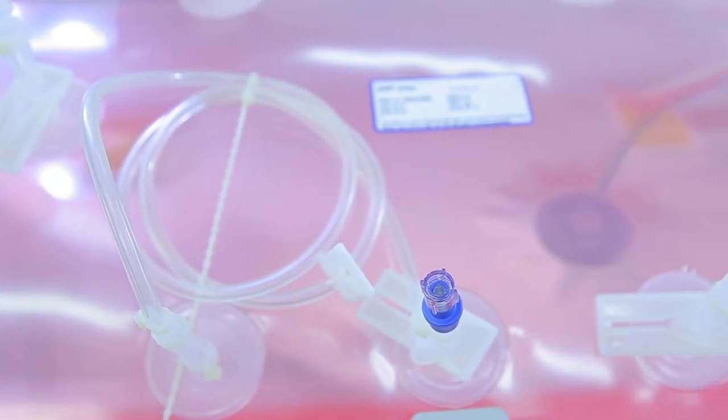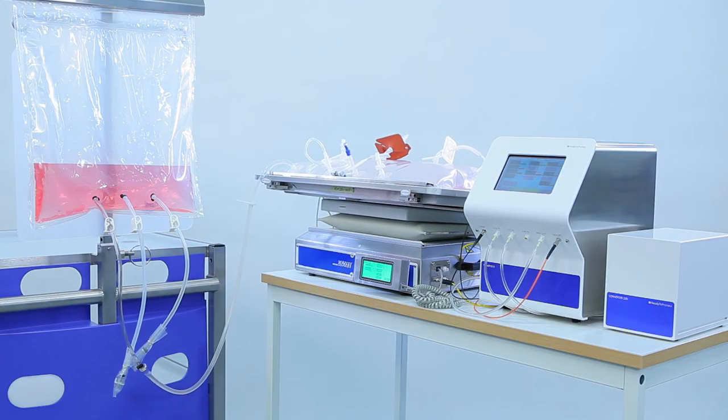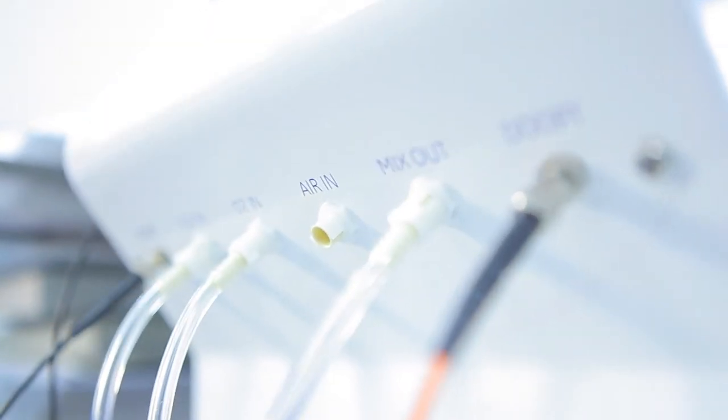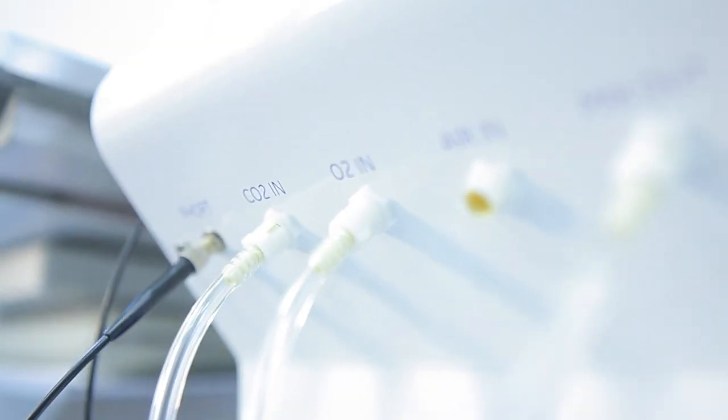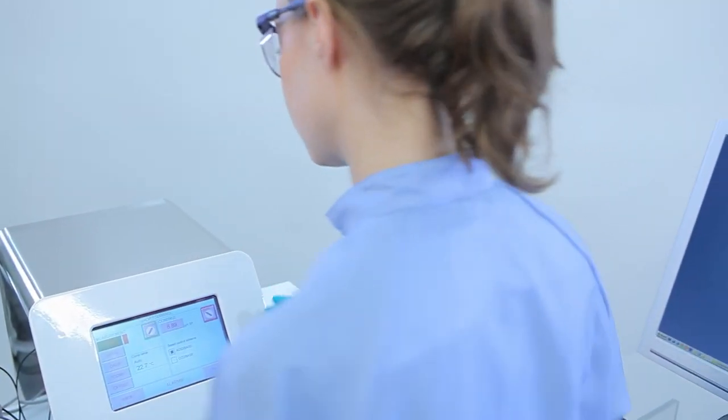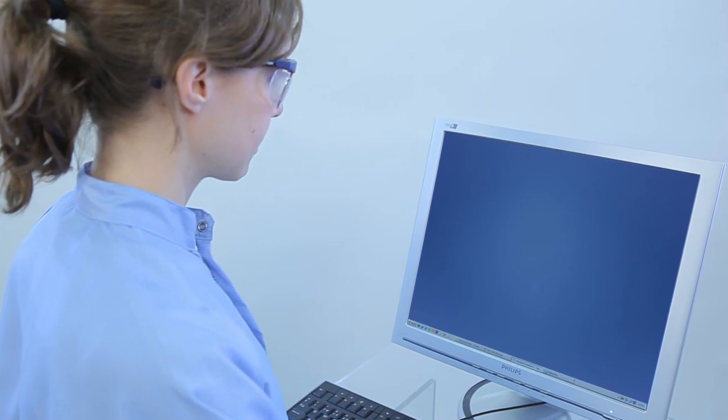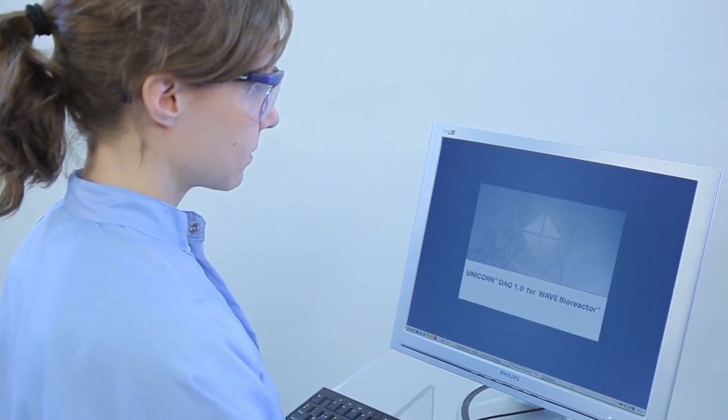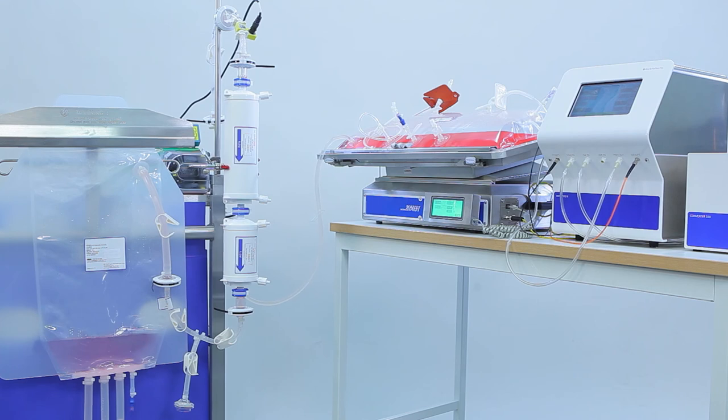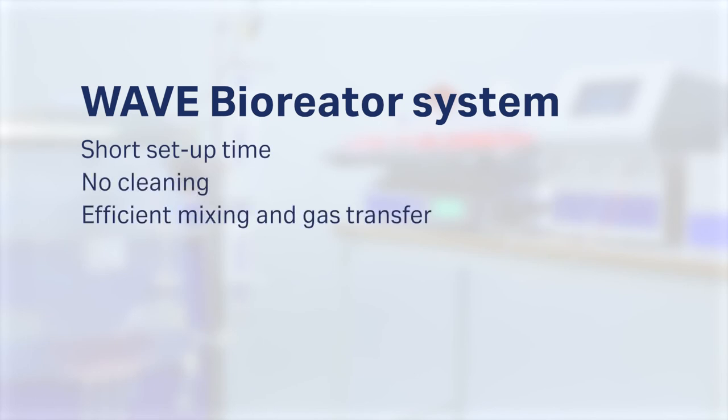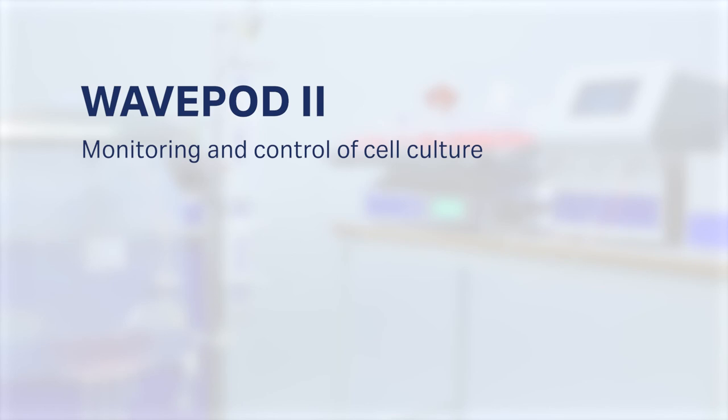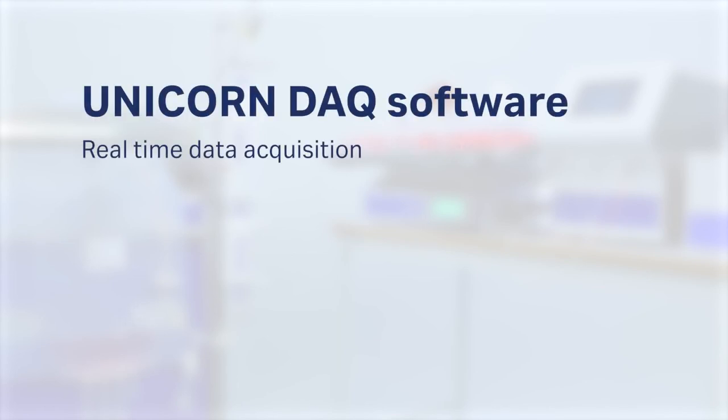The Wave Bioreactor 2050 System is easy to operate and is scalable up to 25 liter working volume and is available for a variety of cell culture applications. The WavePod 2 integrates instrumentation associated with the wave bioreactor system for the setup, control and monitoring of cell culture parameters in cell bag bioreactors. Real-time data acquisition is done using Unicorn DAQ software and allows the user to monitor the run status of any connected wave bioreactor system. Cytiva's ready-to-process platform of ready-to-use products brings flexibility and speed to upstream and downstream processing of biologicals.